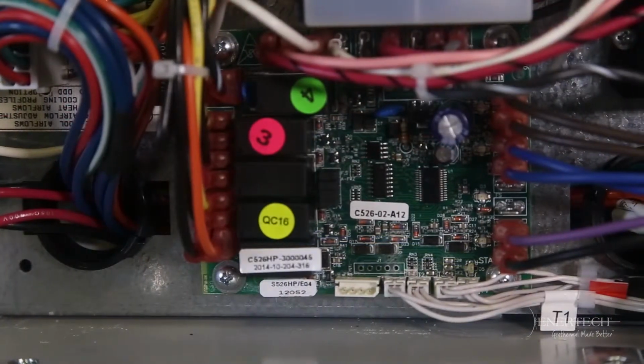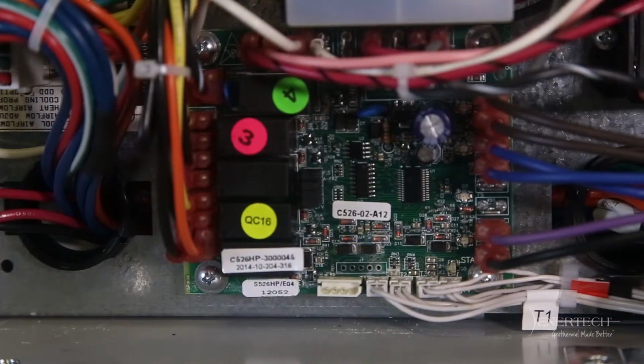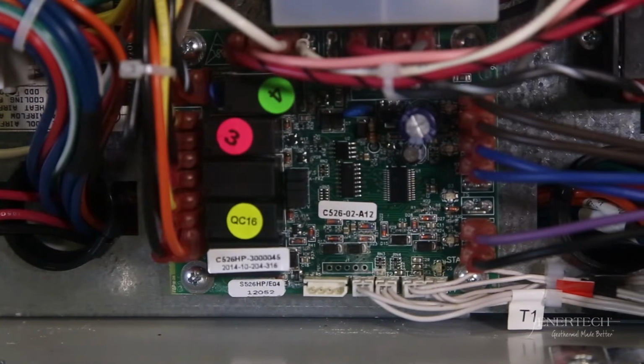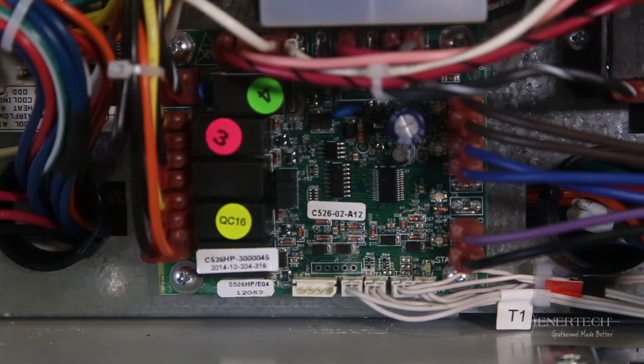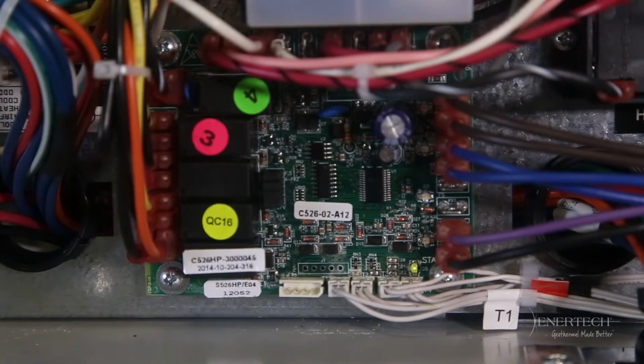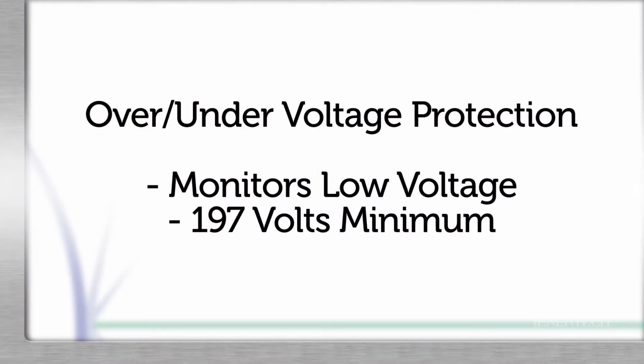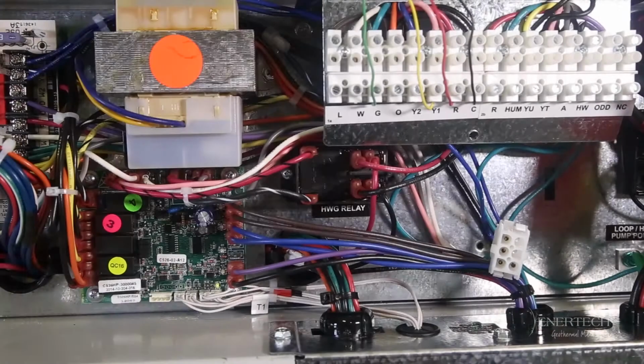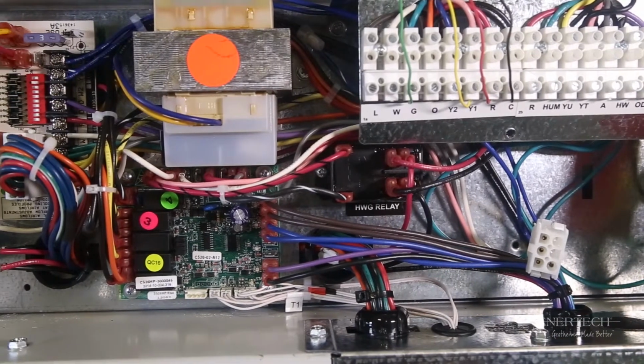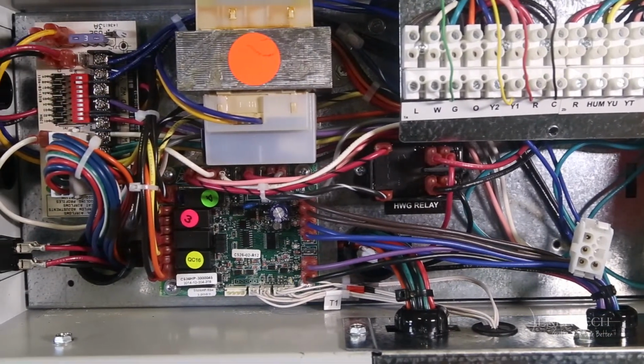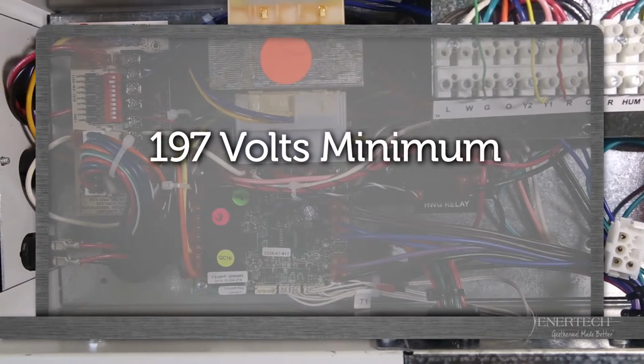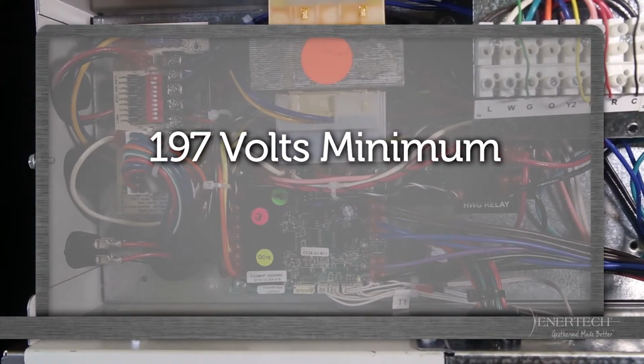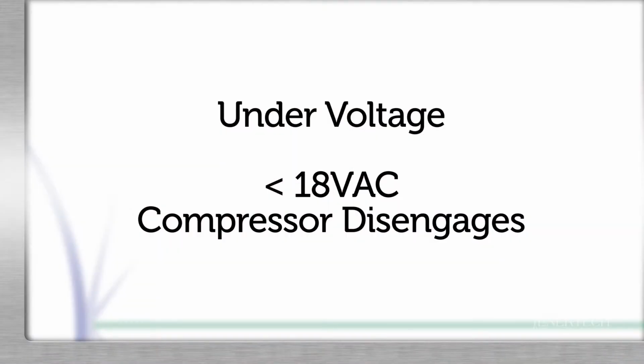The lockout board protects the compressor from operating when an over/under voltage condition exists. If primary voltage is high, so will be secondary voltage. The control monitors secondary voltage, 24 volts AC, to determine an over/under voltage condition is occurring on the primary side of the transformer. For example, if the secondary voltage is 18 volts AC, the primary voltage for a 240 volt unit would be approximately 180 volts, which is below the minimum voltage of 197, recommended by the compressor manufacturer.